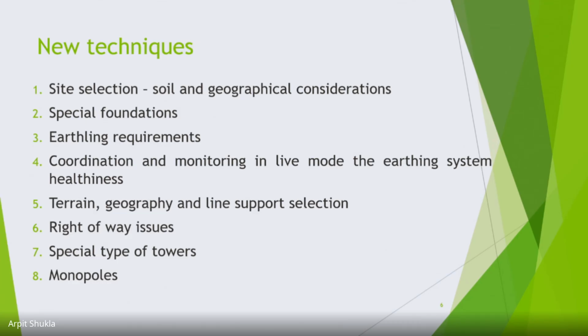Rocky and desert soils are of particular interest. There are types of earthing systems defined in IEEE 80 that are not dependent on wet soil, and that type of earthing needs to be used. When water is not there, the earthing system becomes poor, with very high earth resistance, which leads to failures later on.